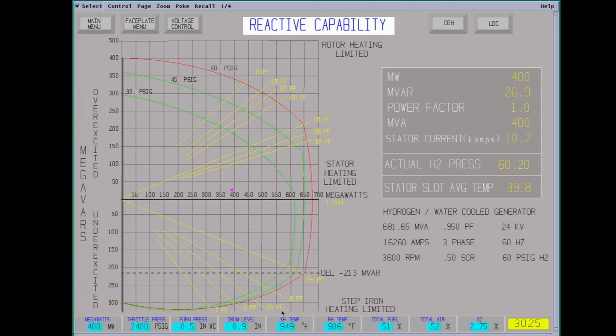Down here, if you're underexcited or bucking, you can have step iron heating. This is the actual metal in the generator's heating up. It's acting kind of like a motor. So it's taking some of the power off the line and changing the power factor on it. Up here, you're boosting, overexciting. Here you have rotor heating limited. Right now you got the megavars, 26 megavars, power factor's 1.